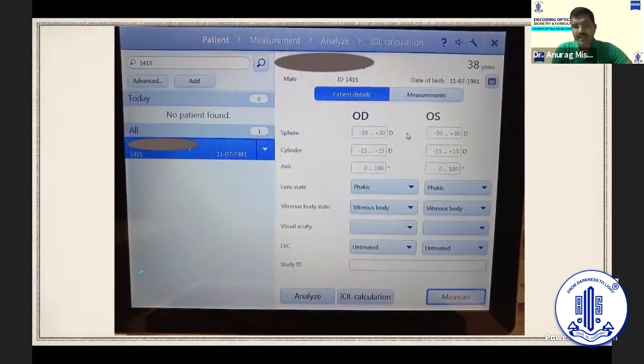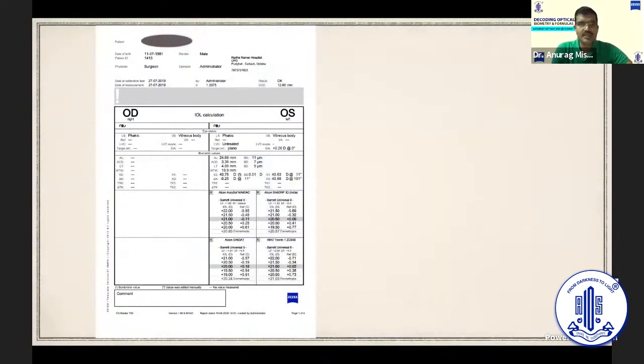This is another patient who had undergone LASIK, but we have intentionally not told the machine that the patient has undergone laser vision correction. We just did the biometry, but the machine caught that the patient has undergone the laser vision correction and gave us an IOL power which was absolutely in the normal range.